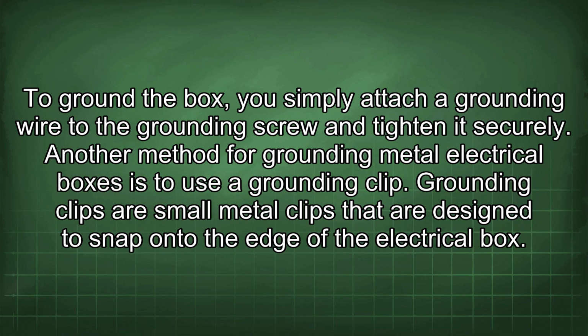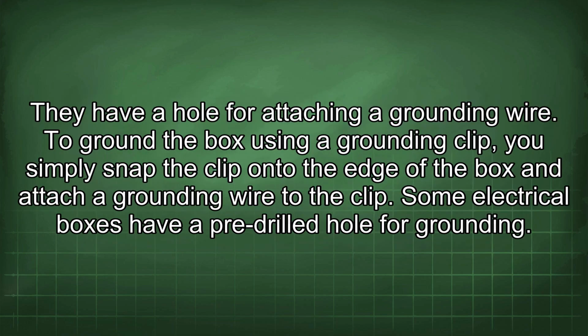Another method for grounding metal electrical boxes is to use a grounding clip. Grounding clips are small metal clips that are designed to snap onto the edge of the electrical box. They have a hole for attaching a grounding wire. To ground the box using a grounding clip, you simply snap the clip onto the edge of the box and attach a grounding wire to the clip.